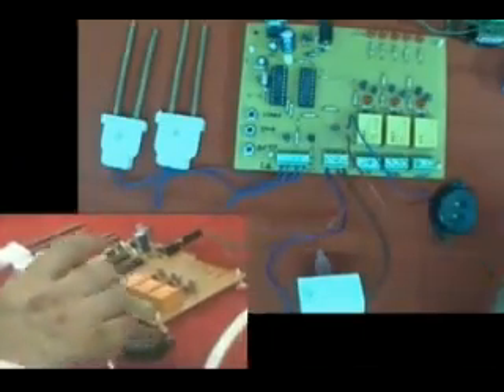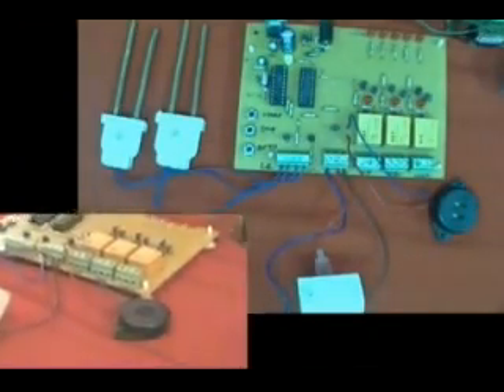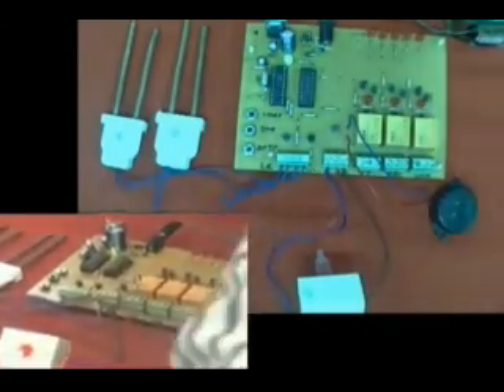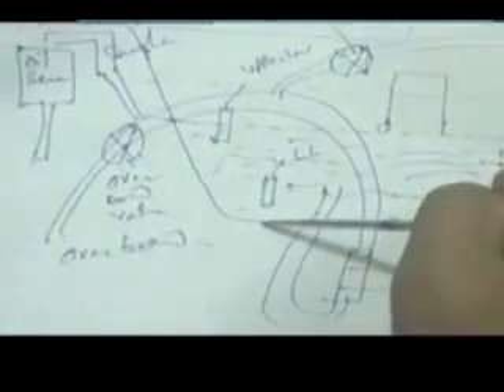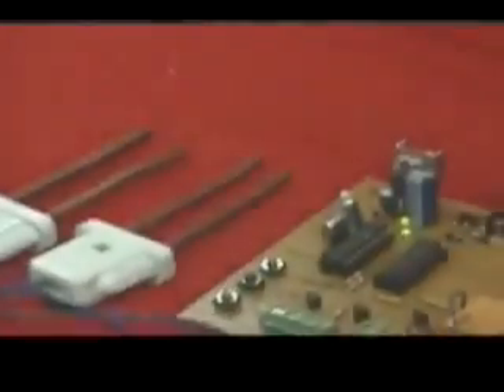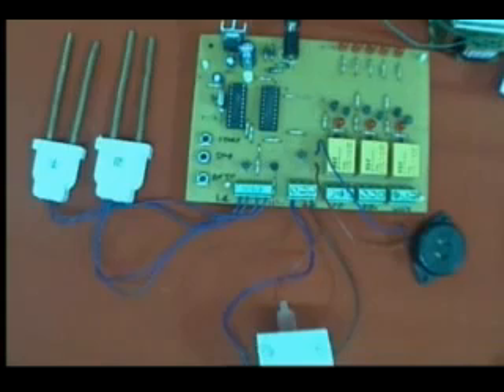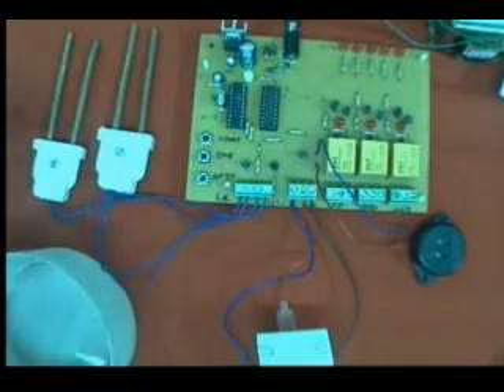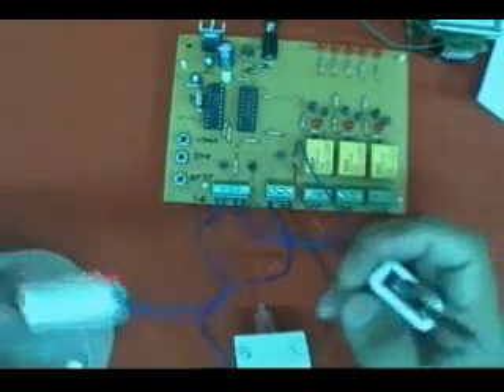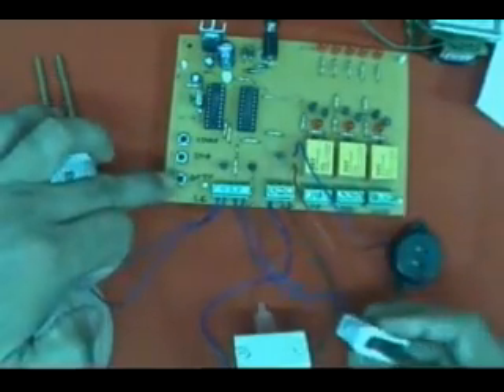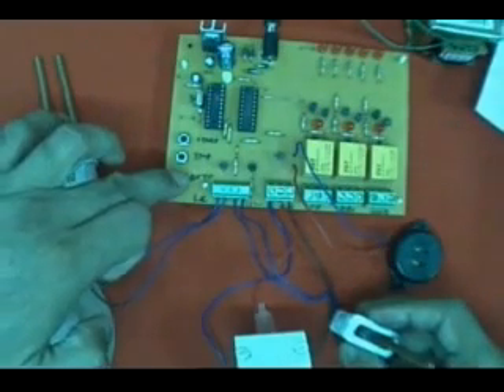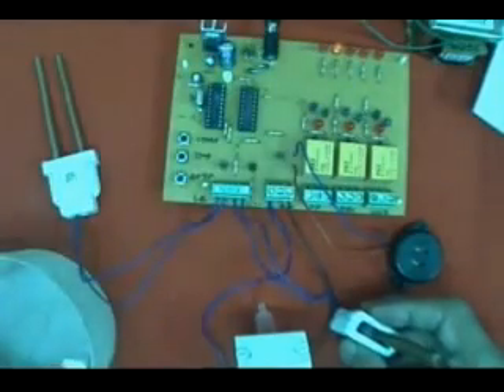Now I will show you how to use this in auto mode. In auto mode, as I explained, there are two level controllers, an upper level controller and a lower level controller. Whenever the bilges become full and the level becomes high, this process is repeated automatically. So to show this in the classroom, we have a little water inside a pot, and this is the low level sensor, but before that we have to put it in auto mode. So press this auto button. When I press this auto button, this LED becomes on, which says the plant is in auto mode.